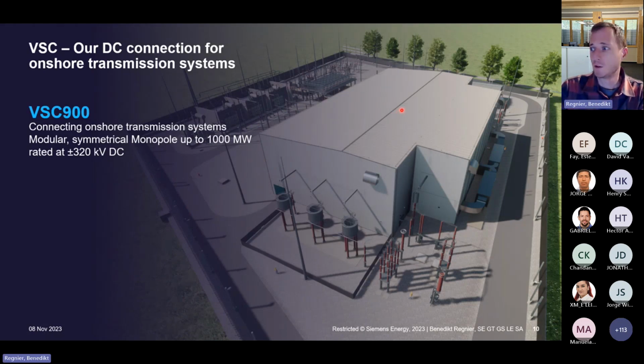We introduced some kind of clustering names. We have here as an example the VSC 900. That is a symmetrical monopole up to 1000 megawatt, typically at plus minus 320 kV. When a customer approaches us with an idea for an HVDC, with these building elements we can very fast generate a layout, generate a single line, and provide a possible solution for the customer. We also support in finding the best solution for the situation, because there is always more than one solution possible.